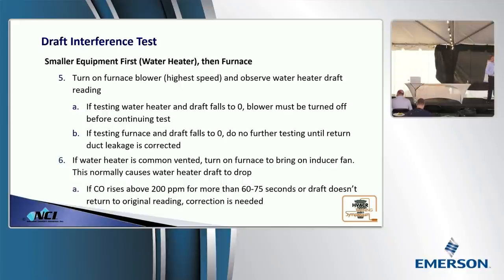Fix it. You also need to check the impact of the water heater if it's common vented with an 80% furnace. It will probably drive the draft down the first 60 seconds. It should recover and then start to take off as a result after that. But if your CO readings continue to climb for up to a minute, minute and a half, you got problems. Draft hasn't recovered and you need to see what's going on.